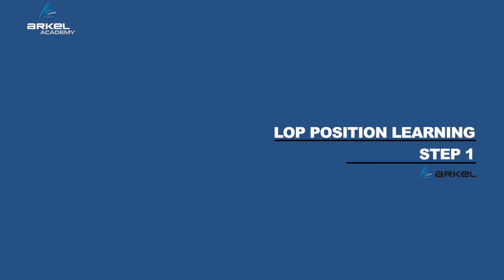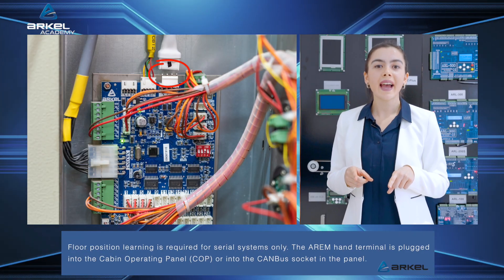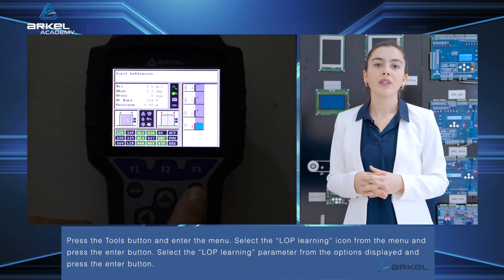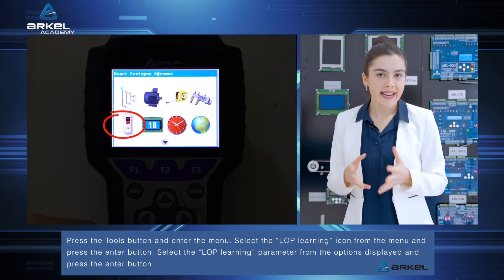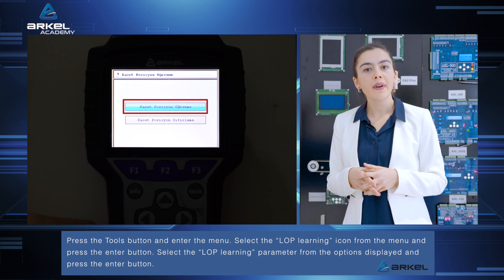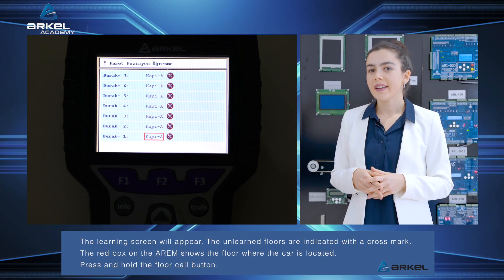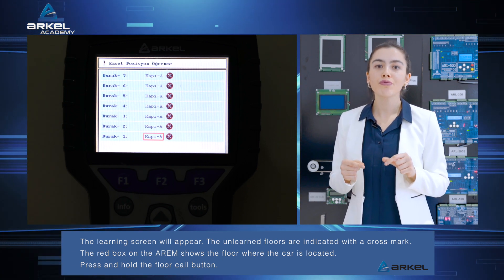LOP Position Learning: Floor position learning is required for serial systems only. The AREM hand terminal is plugged into the cabin operating panel (COP) or into the CAN bus socket in the panel. Press the tools button and enter the menu. Select the LOP learning icon from the menu and press the enter button. Select the LOP learning parameter from the options displayed and press the enter button. The learning screen will appear. Unlearned floors are indicated with a cross mark, and the red box on the AREM shows the floor where the car is located.